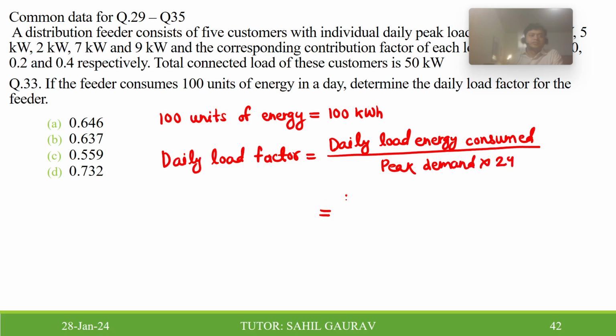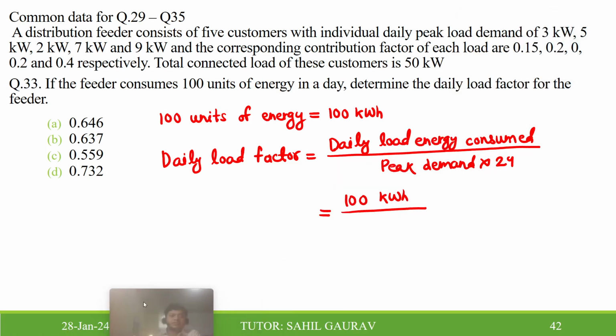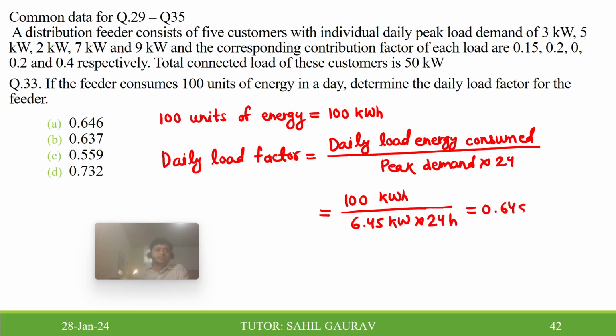So daily energy consumed is 100 kilowatt hour and peak demand we have calculated in the previous part, that is group peak demand. That is coming as 6.45 kilowatt. In question number 29 we have calculated. So 6.45 kilowatt and number of hour is 24 hour. So we will get 0.6459, approximately equal to 0.646. So A is correct one.